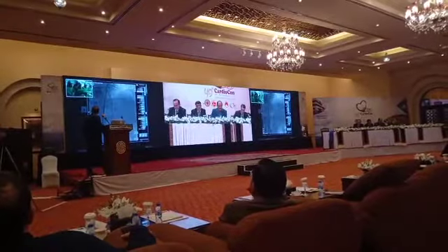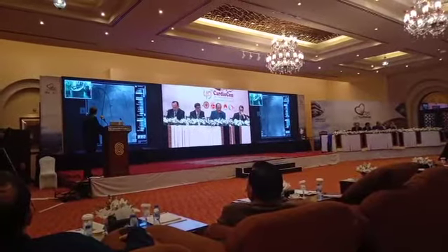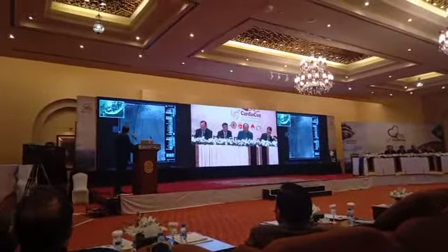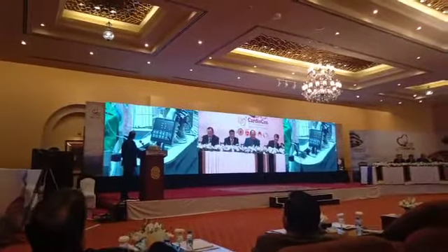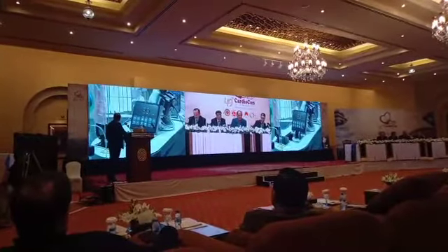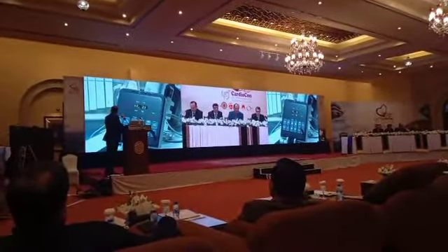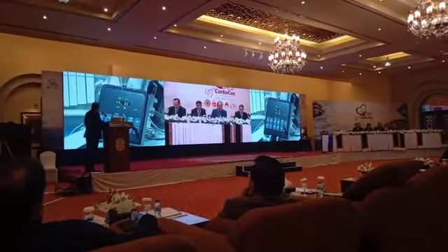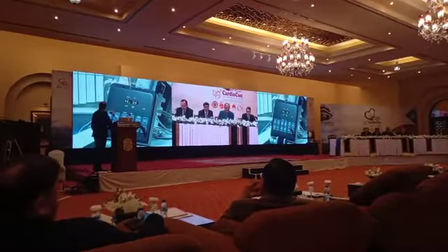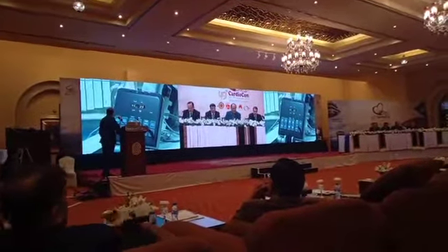So I'm going to just get you to focus in on the console now. So if you start advancing the catheter, please. And so what you can see there are two important things to note here. On the left, you can see that there is a fluence rate, and that is measured in millijoules per millimeter squared. And essentially that is the amount of energy that we are going to deliver within the coronary artery. The other thing on the right-hand side is the frequency, or the rate, so the number of pulses that we will deliver and generate in a second.